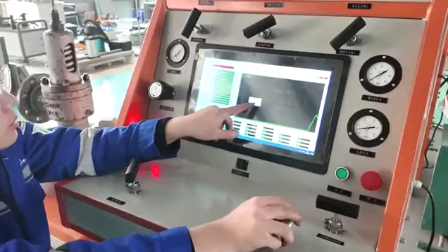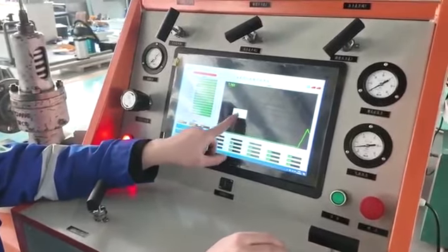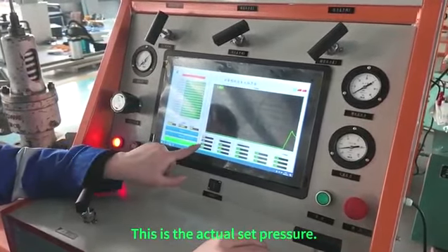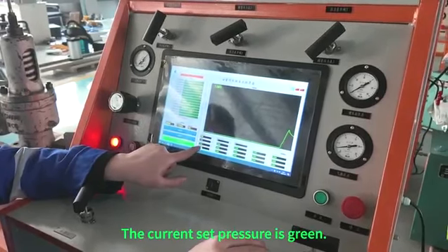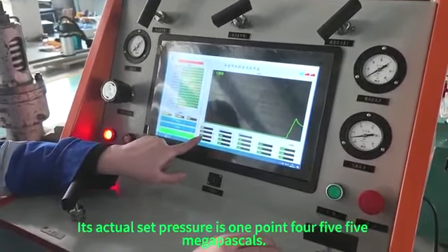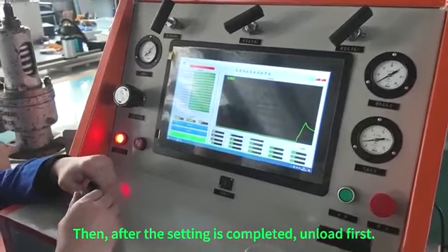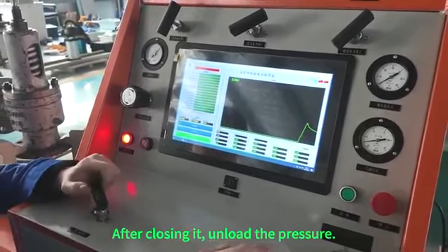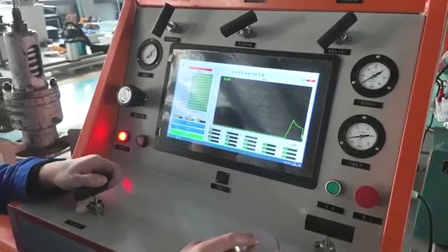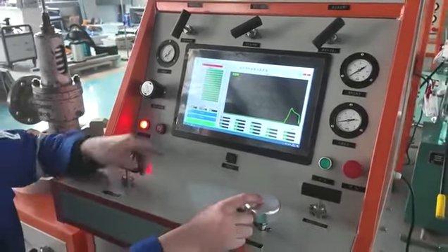Okay, it's over. Click confirm. This is the actual set pressure. The current set pressure is shown in green, and the green one is something we can't change. Its actual set pressure is 1.455 megapascals. After the setting is completed, unload first. After closing it, unload the pressure. When the pressure gauge is almost zero, then you can close it.